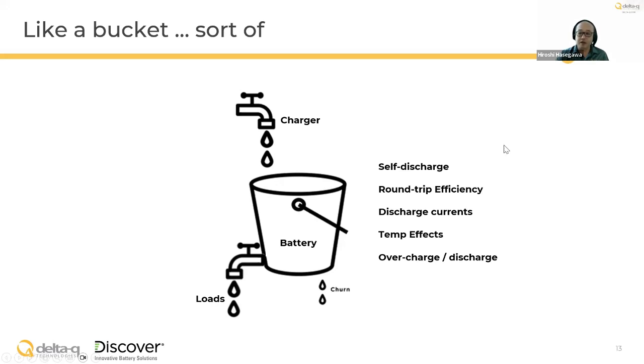As for overcharge and discharge, lead acid battery technologies have improved and are generally more forgiving when overcharged and discharged from time to time. Some chemistries are more forgiving than others—flooded and gel tend to be more forgiving, whereas lithium charging behavior is generally restricted by the BMS just for safety purposes.